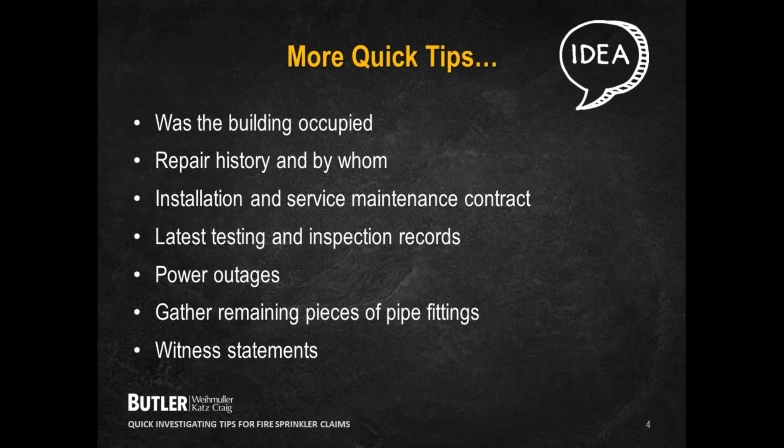You see it sometimes, though, that the insured would contract directly with the fire sprinkler contractor, so you'll need to gather all those documents. You'll also need the latest testing and inspection records. Those would be obtained from a fire service maintenance contractor. It would be similar to your maintenance contract.